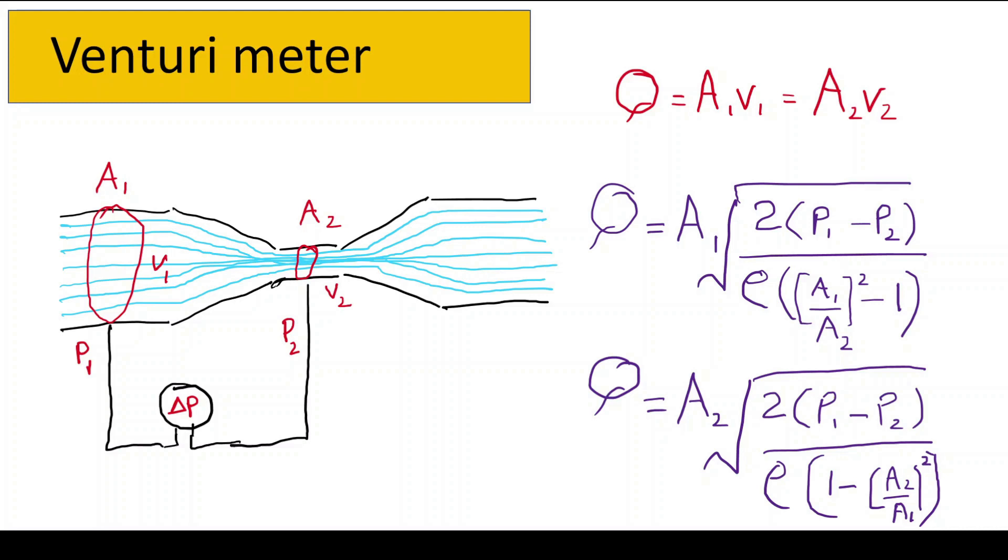Well, venturimeters are commonly used in various industries including chemical process industry, oil and gas, water and wastewater applications where flow rate measurements are crucial for process optimization and control. Here I would like to emphasize that these flow meters are particularly useful for measuring the flow rates of clean liquids or gases. Moreover, they may require calibration or correction factors to account for different flow conditions and fluid properties.